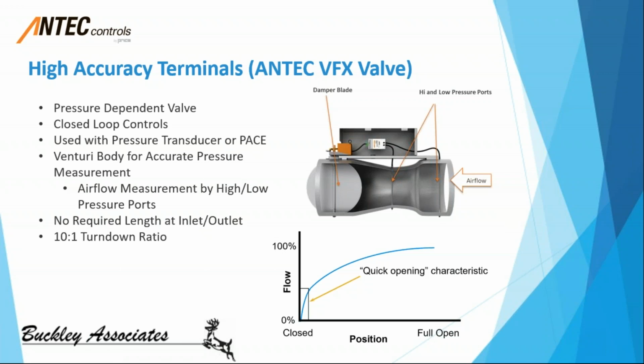So the second type of air control device we're talking about is a high accuracy terminal. This functions very similar to a standard VAV box. It uses the exact same closed loop controls, and it remains, again, a pressure dependent system. However, the device can more accurately measure the airflow due to the Venturi body. The only thing that changed here is instead of using the same diameter ductwork running through this entire valve, now we're using a Venturi body.